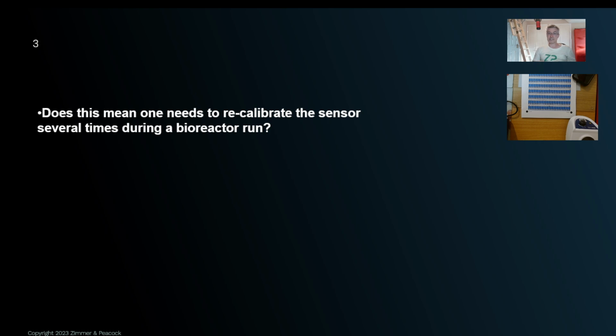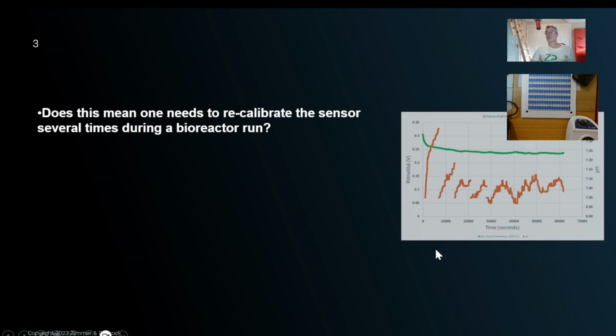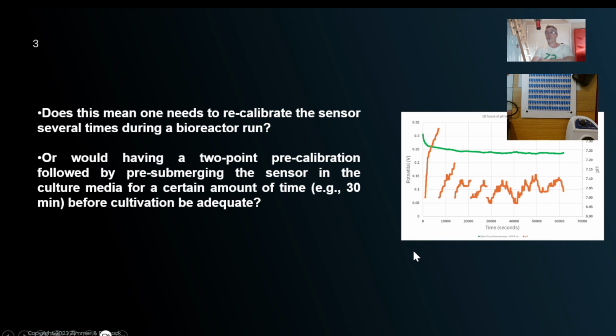I think you can see the way that a pH sensor went into that solution, it changed its open circuit potential. But of course, what you say in your next question is, or having a 2 point calibration, pre-calibration, I would play with some of the ideas that you have here, doing a 2 point calibration and then a pre-submerging. I would actually argue doing the pre-submerging and then the 2 point calibration is a good idea.